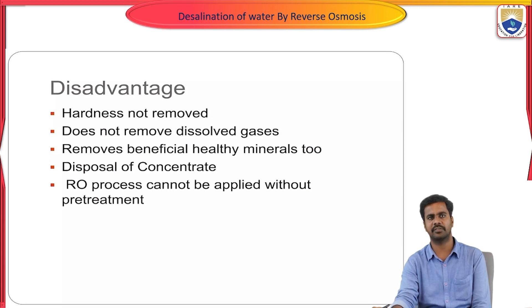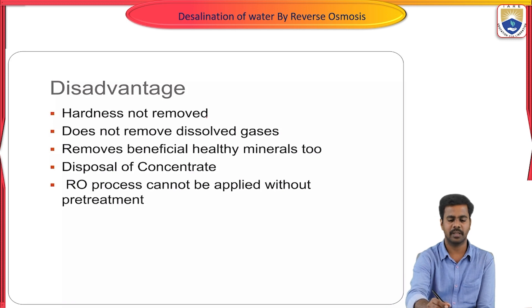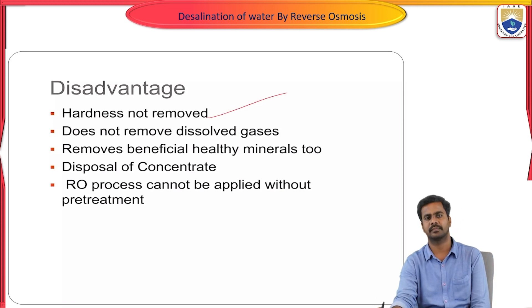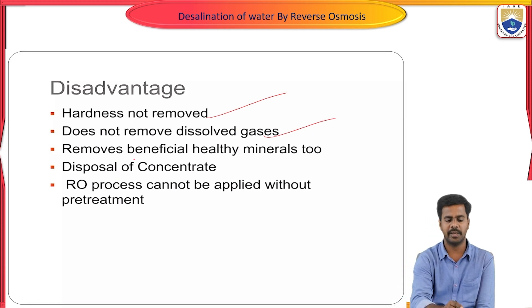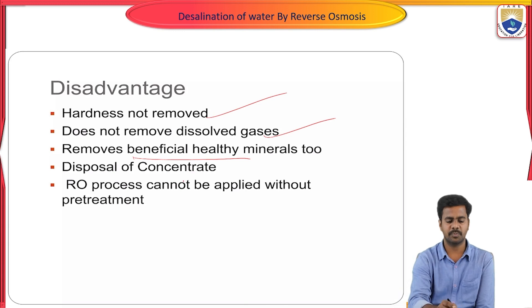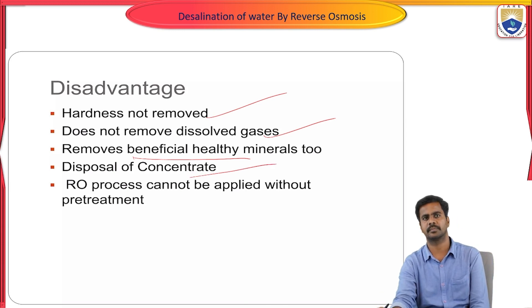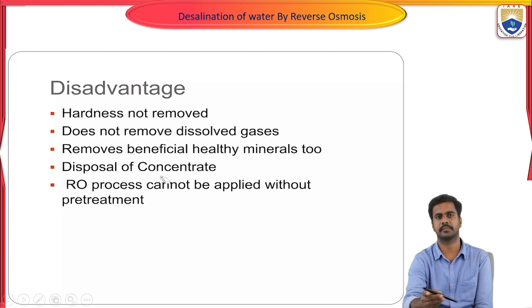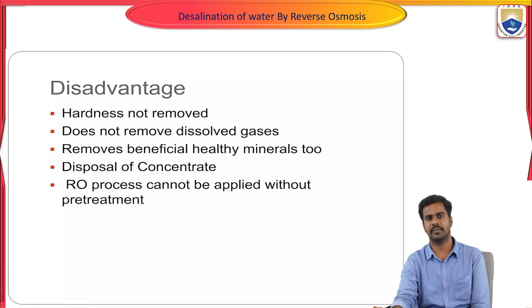Coming to the disadvantages of reverse osmosis: by using this method, we cannot remove dissolved gases, and in some cases it removes beneficial healthy minerals too. There is also concern about disposal of concentrates. Additionally, reverse osmosis cannot be operated without pre-treatment — it does not work without pre-treatment of the water. These are the disadvantages of reverse osmosis.